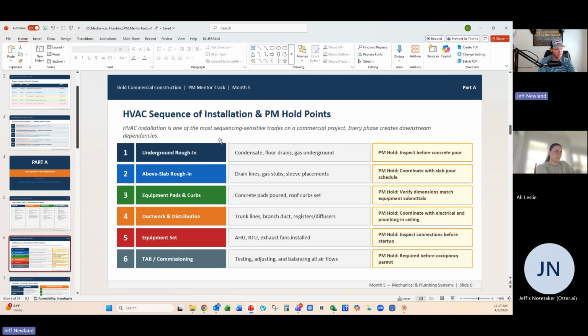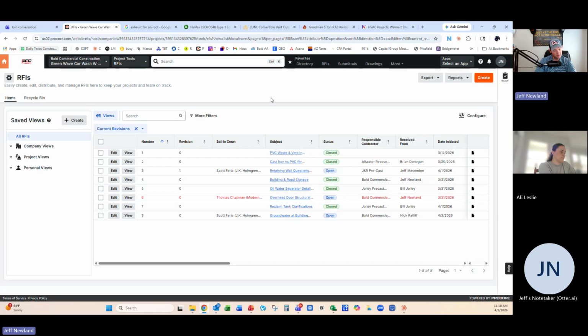So then your concrete pads - that's another word. Anytime we have a piece of equipment, it needs to sit on what's called a housekeeping pad. So a housekeeping pad is going to be, like on our car washes, the mini splits, the condenser that sat outside, sometimes they sat on a pad of concrete. Sometimes they sit on a rack that bolts to the concrete if it's on a sidewalk. In the back room, we didn't have any housekeeping pads in our car washes, but you'll commonly see one for your transformers - our transformer was on the second floor. You'll also see housekeeping pads for hot water heaters, something like that.